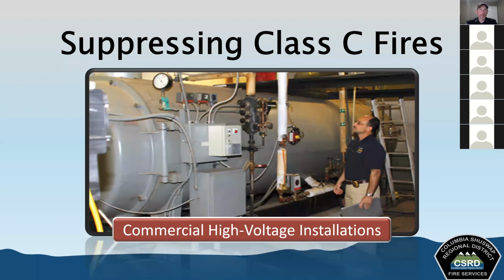So now there are commercial high voltage installations. These can house in excess of 600 volts. Usually they're housed in vaults or fire resistive rooms. They'll have high voltage warning signs all over the doors. Again, water doesn't get used because we could damage the electrical equipment that's not involved in the fire, and we conduct electricity, which could end up hurting us. The smoke from the fires contains very toxic chemicals, from the plastic installations and the coolants that are used there. Typically with these areas, we're looking at a confined space. So if we don't have confined space training, we're not going in for that.